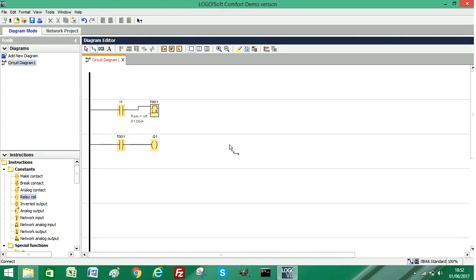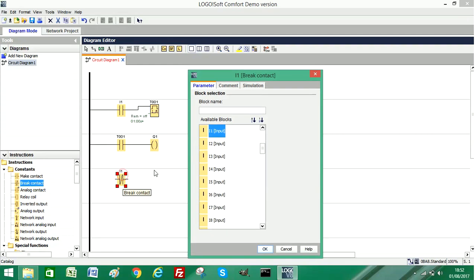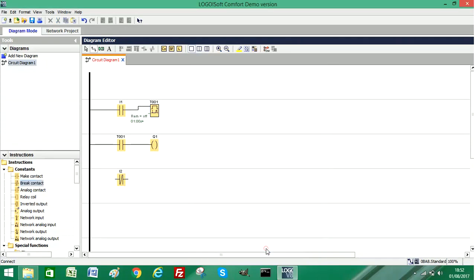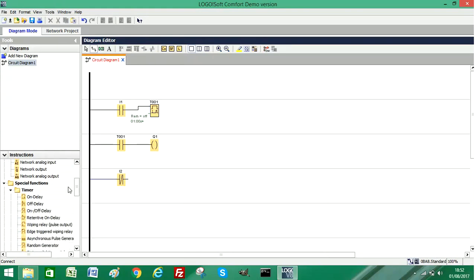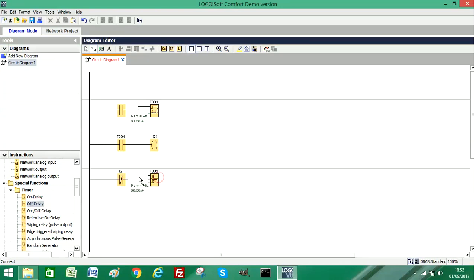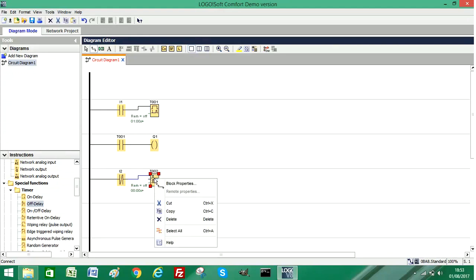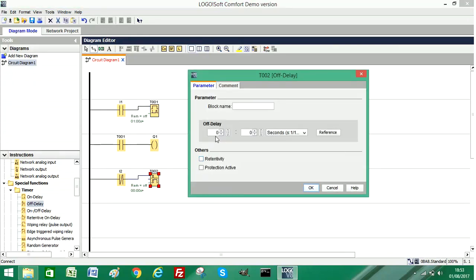I'll just leave that as Q1 for now. Now the second part of the pulse generator: I'm going to add a break contact or a normally closed contact. I'm going to just select the second input for now. Then I'm going to add an off-delay timer. I'll connect it to the timer trigger and again set this timer to a time of one second.